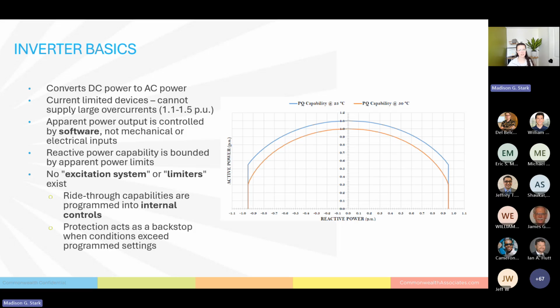What you see over here on the right is a reactive power, active power, so a power capabilities curve for an inverter. This is just a sample. They generally follow this general shape, where they have a rounded top, and then they have kind of these steep cutoffs on either side that are their reactive power limits. These inverters do not have an excitation system, and they do not have the limiters like you see with a synchronous generator. So their ride-through capabilities and their limiters are all controlled by their internal controls, their internal programming. The external protection that you see, similar to a synchronous generator, acts in very much the same way, where it's a backstop. When operating conditions exceed the programmed capabilities, then these protection systems are going to act to protect all the equipment in the system.